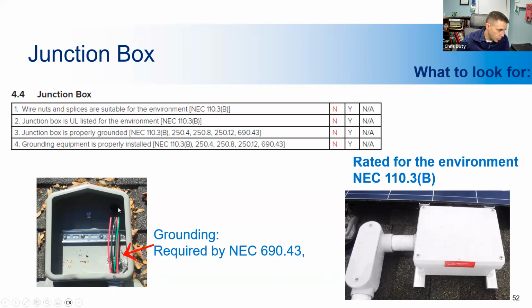You can see the green wire, which is the grounding wire, is going right through this junction box, and it's not bonded to the junction box. So if the sheathing on this wire wore down, this could get exposed to the conductive wire, and it would be conductive at that point, and that could make it unsafe. But if you ground it, then it should still be safe. And in the box on the right, this box is non-metallic, so it doesn't have to be grounded. And in both pictures, the enclosures have to be rated for the environment they're installed in.